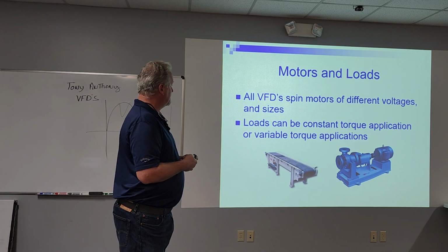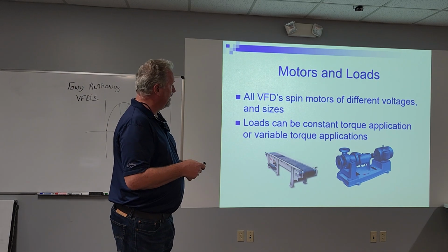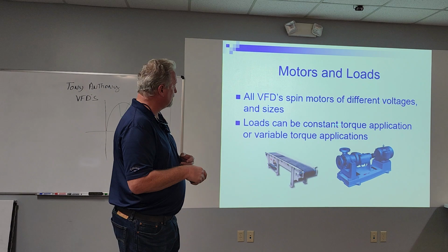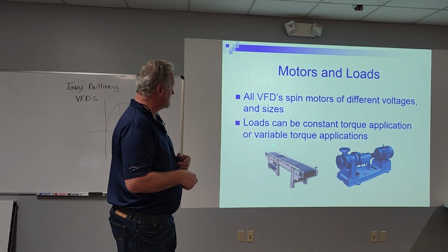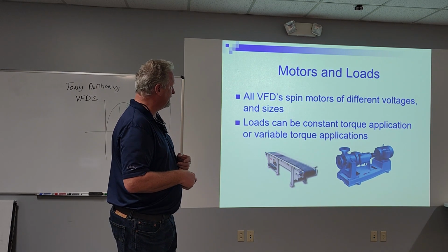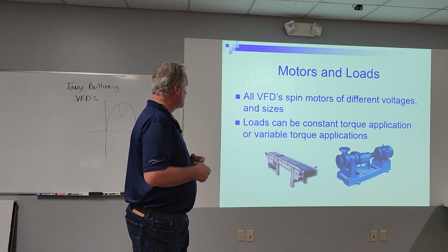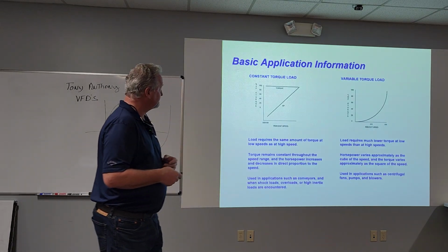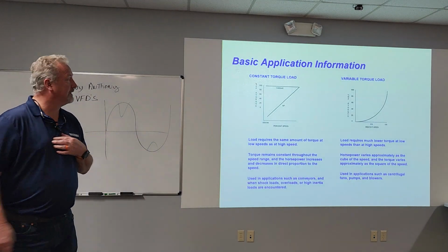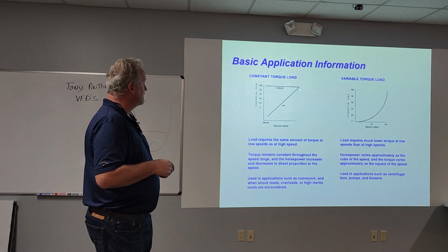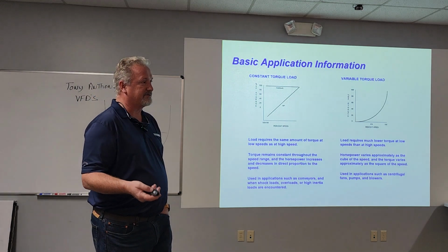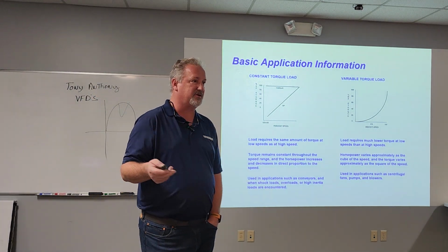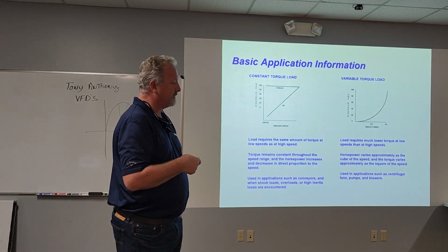Boom, motors and loads. We're going to talk a little bit about loads, and we're not going to spend a lot of time on constant torque because that's more industrial, and variable torque. But this is why we're here, and this is the biggest reason drives exist: variable torque loads. A constant torque load is more of an industrial thing. Centrifugal pumps and fans are called variable torque loads. But a constant torque load is something like a conveyor.